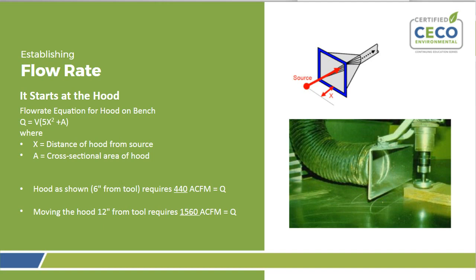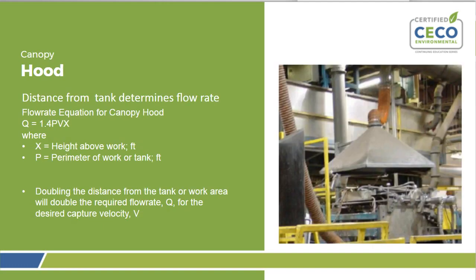Again, we have the equation that can be utilized, and there are various equations for different types of hoods relying on capture velocity. Here we can see the equation is Q equals 1.4 times the perimeter of the hood times the velocity times the distance x. So if we just double that distance x, you are going to double the flow rate required. So it's a very, very simple concept for these capture hoods that rely on capture velocity to have them close to the source.